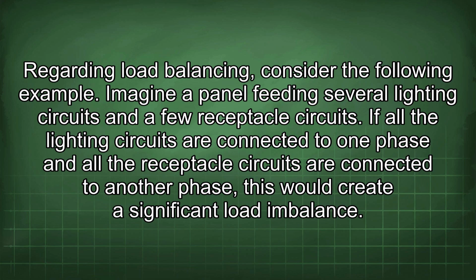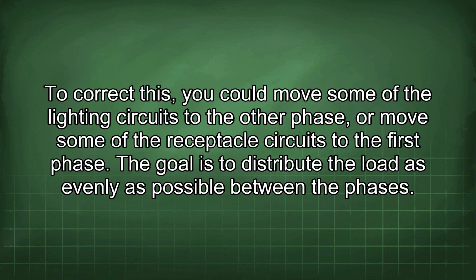Regarding load balancing, consider the following example. Imagine a panel feeding several lighting circuits and a few receptacle circuits. If all the lighting circuits are connected to one phase and all the receptacle circuits are connected to another phase, this would create a significant load imbalance. To correct this, you could move some of the lighting circuits to the other phase or move some of the receptacle circuits to the first phase. The goal is to distribute the load as evenly as possible between the phases.